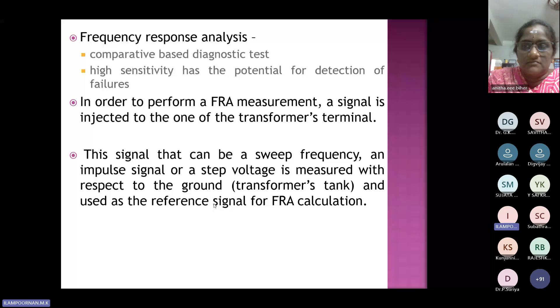So all these things can be taken from this FRA. This is the connection - usually people do it like this. You can see I am injecting the voltage here, and you can take a reference signal, either from the end of the bushing - that is the earthing connection to the bushing - or from the tank itself directly. You apply to one winding, short the other two windings, connect them to earth, and measure with some measuring devices. You can calibrate this voltage to current, and that is what you are observing here.